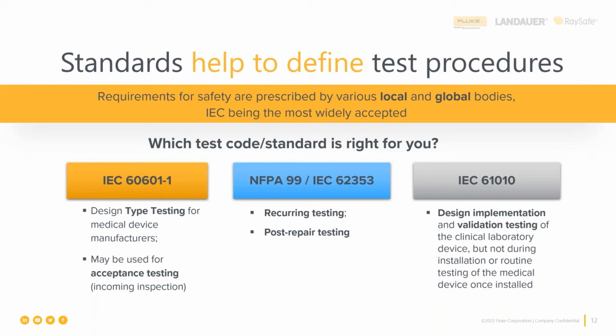The next standard underneath the umbrella, having to do with electrical safety, is the IEC 62353. So for all of you out here in Asia Pacific, ignore the NFPA 99. That is a US only code. It's not a standard. And the IEC 62353 is designed for use in recurring testing. That is every year, after each repair, and the next and the next. And that's because it has been specifically designed so that it does not shorten the useful life of the medical device. The IEC 60601-1 does or may. So keep that in mind.